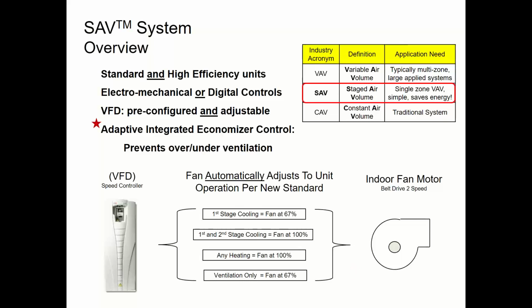It's not going to matter anyway, Mike, because when we get to the economizer, you're going to see that I'm not even going to be able to have a separate airflow set point for the heating than cooling on a package system. But if you were doing a building automation controlled system with your own stuff, then you could do it, but you'd have to look at the manual to figure that out. If anyone needs help with that, let me know.